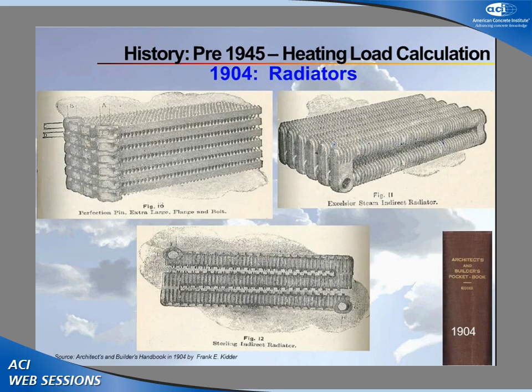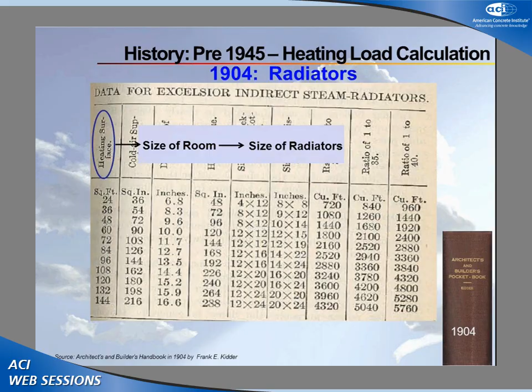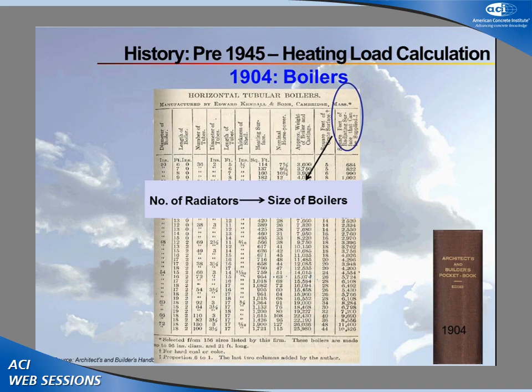In 1904, for example, in Kidder's book, there was a lot of information on steam radiators, since steam heating systems were fairly common at that point. You picked a particular room size, and it told you how many radiators you needed, regardless of where it was in the United States -- most things were sized more or less for the middle of the country. Once you knew how many radiators you had, you could size the boiler based on their size and number.